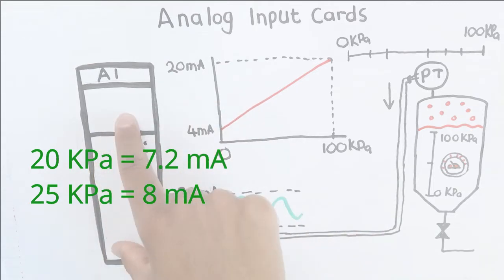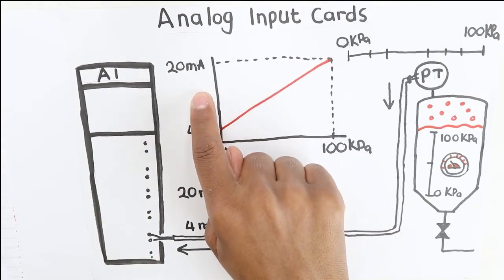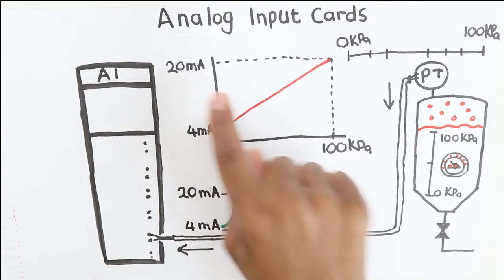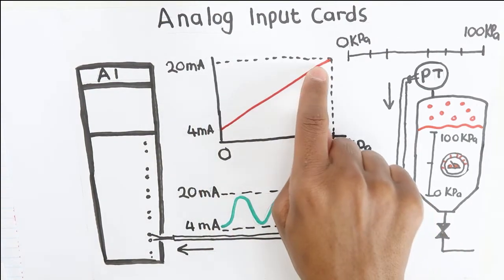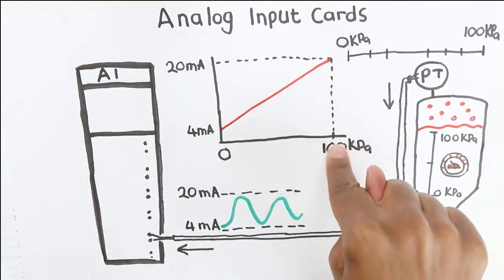If the pressure is at 50, the milliamp signal will be 12 milliamps. If the pressure is at 75, the milliamp signal will be at 16 milliamps. And of course at 100 kPa, the pressure signal will be at 20 milliamps.